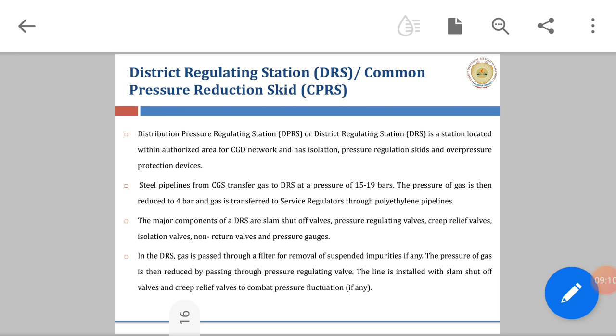As shown in the figure, which I will come to next, the DRS twin stream model has two regulating devices, the monitor and the active regulator, with a 50% redundancy. The monitor is installed to assure continuous gas supply in case of failure of the active regulator. Usually in two streams, one line is working while the other line is on standby. A creep relief valve is installed in the line to release the excess pressure in case both active and monitor fail. Then we have the CRV, which releases excess pressure.